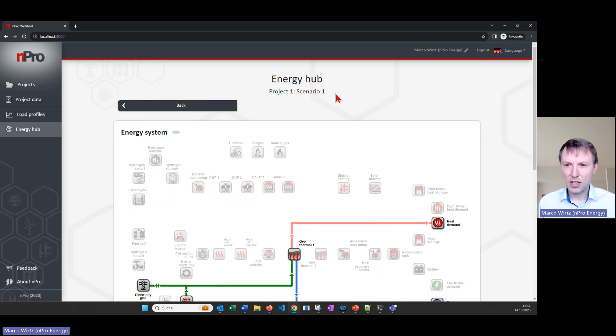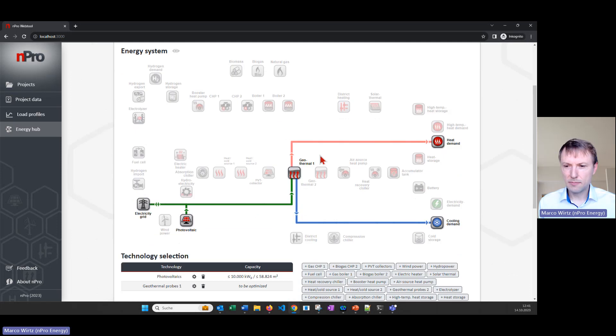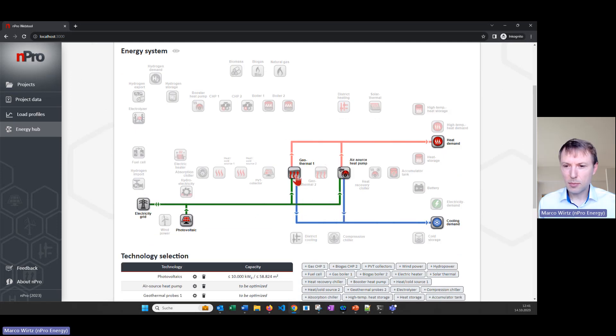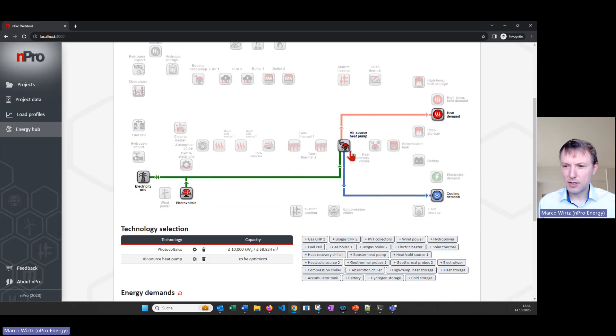And then we go to the second part, the energy hub, where we define how do we cover the heating demands and the cooling demands of the building. And here we want to use the air source heat pump, we deactivate geothermal source and then use the heat pump for covering the cooling loads and the heating loads.